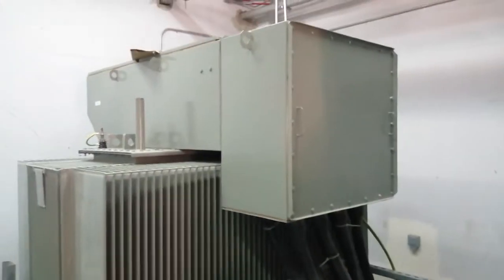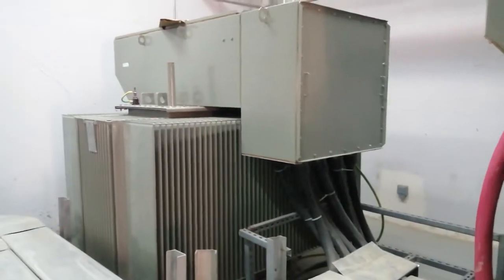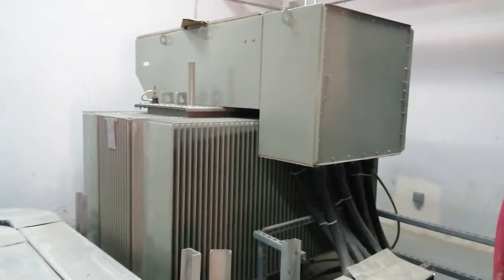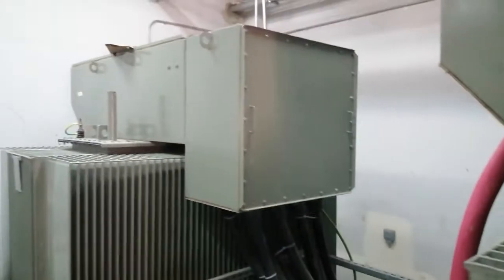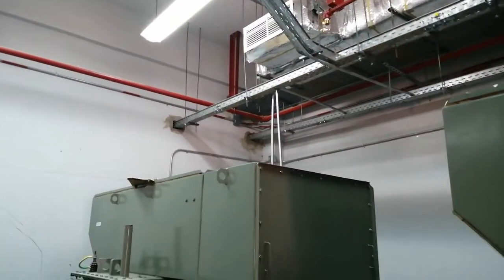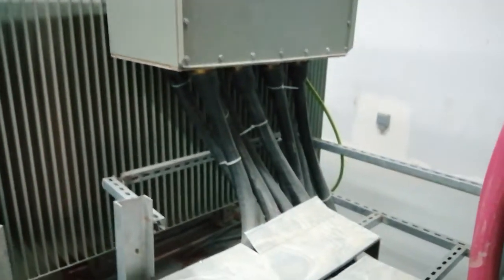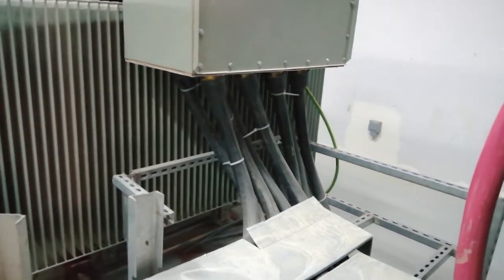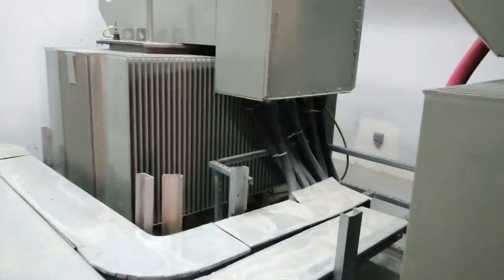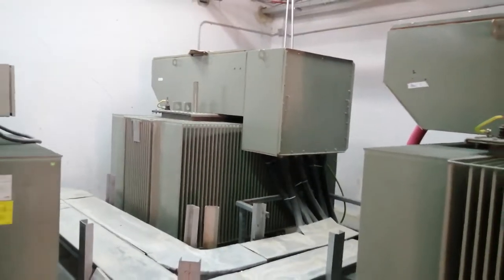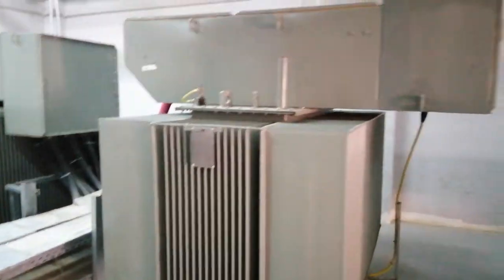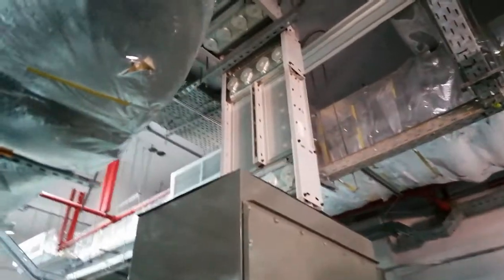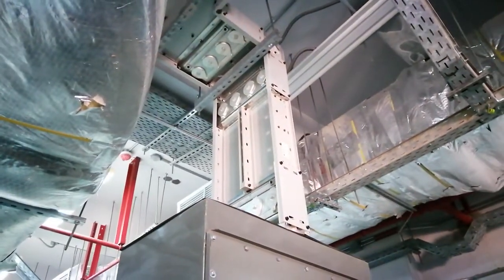This transformer has the old concept, you see, the old concept, meaning cable concept: incoming is the same medium voltage, outgoing is from this box, not from the busway. See, nothing going up, going by cable like this. And this is the difference between the cable and busway. This transformer is by cable, and this transformer is not by cable, by busway. This just wants to help you understand what the busway concept is, just to reduce the cable size.